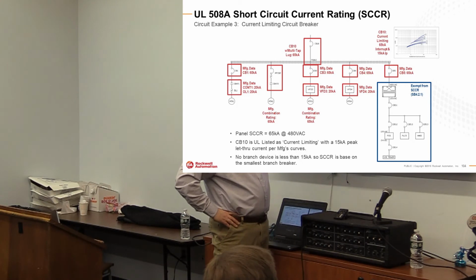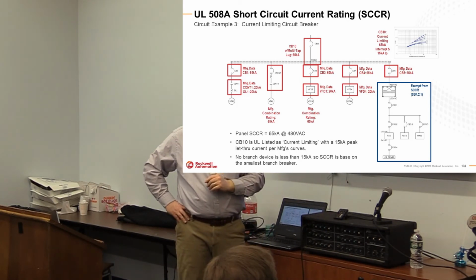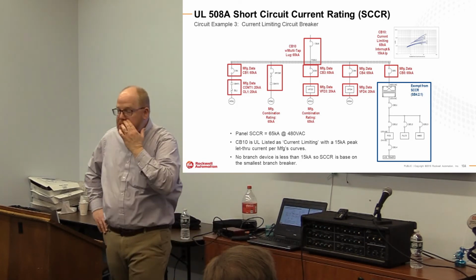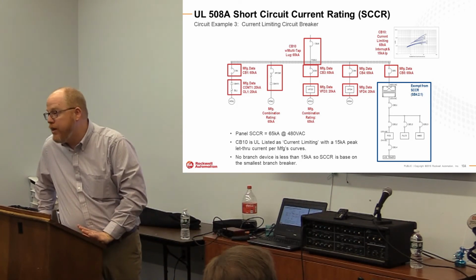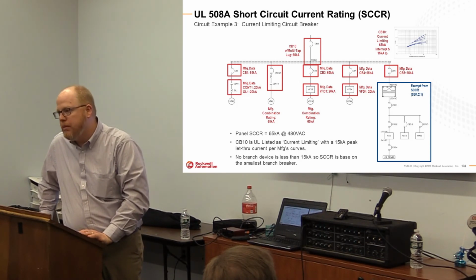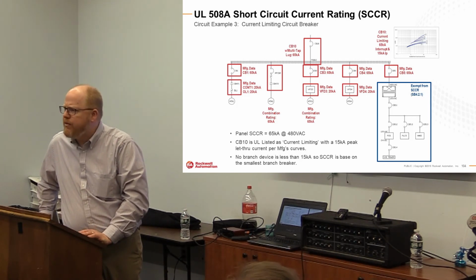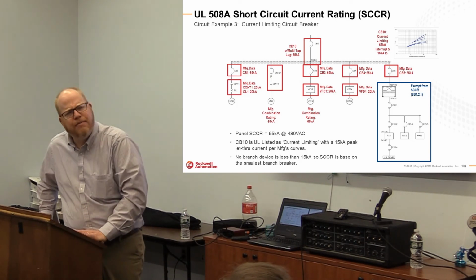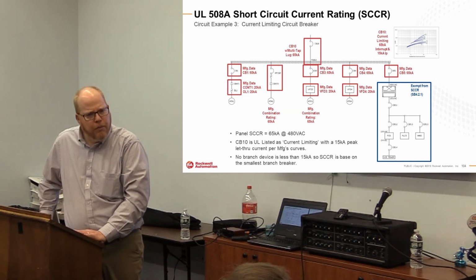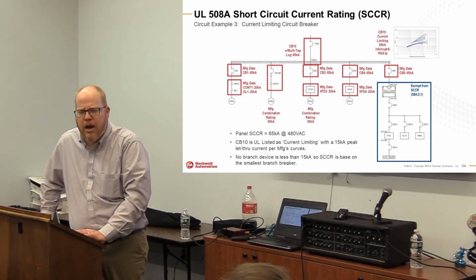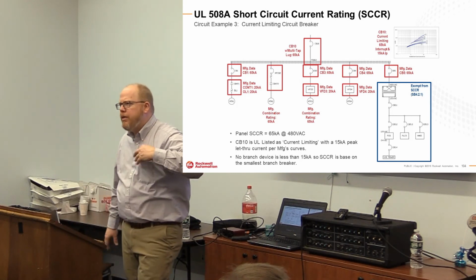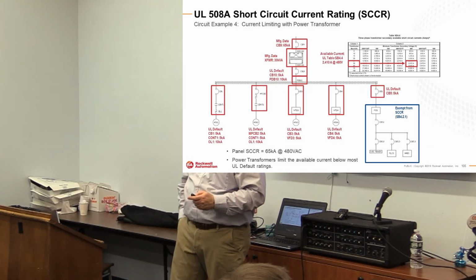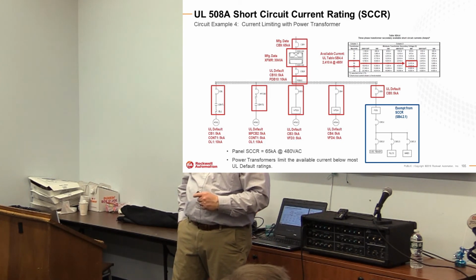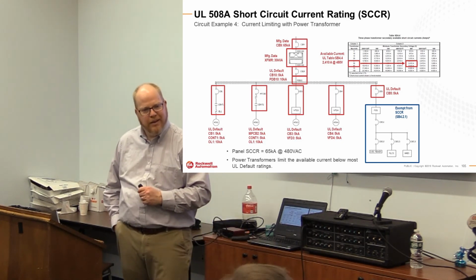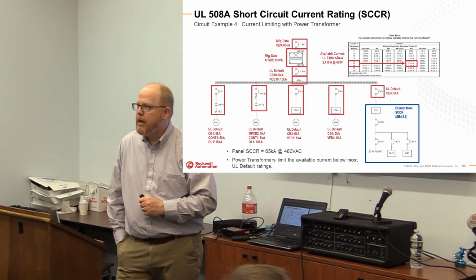So if your customer gave you a requirement, they only wanted a 20,000 rating, you would change the main breaker to max? Oh, yeah. To lower that? Absolutely, and then if they're giving you, I mean, that's a reasonable bogey. 20,000 is reasonable. You probably would not even need to mess with current limiting rules, honestly. Yeah, I find 25 or 35 is very reasonable. I remember when somebody did the math, like the real math, on what available fault is at really 65, the size of the transformer was astronomical. I mean, it's crazy. I think it's probably more around 25 to 30 is a reasonable number. Then just to make sure your let through doesn't, yes, yeah, that'll iterate back down. Yeah, that goes down everything, all the branches.